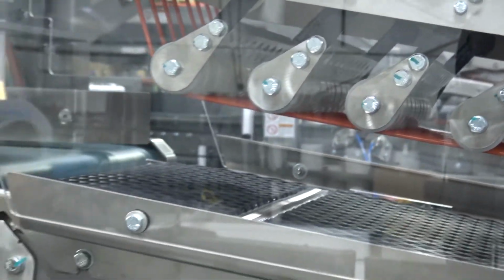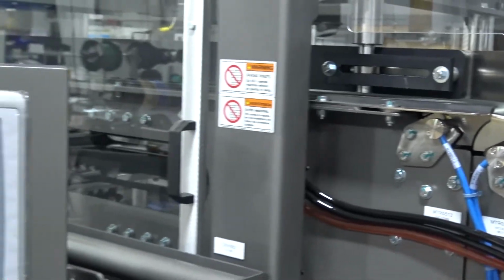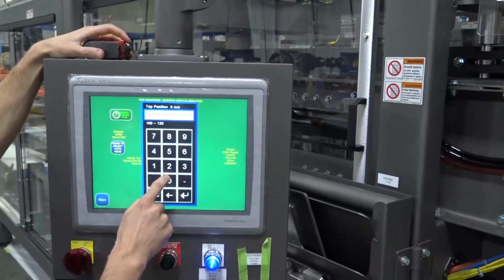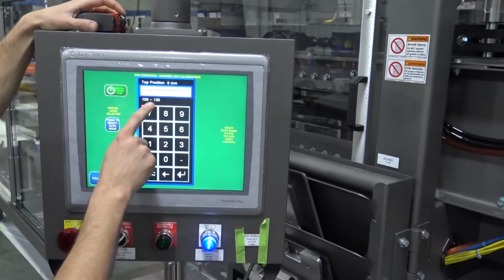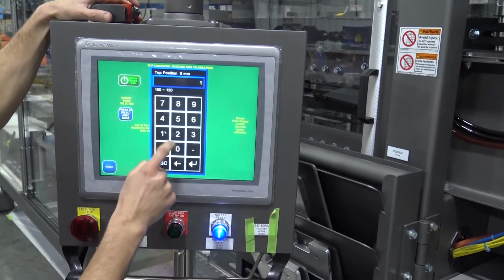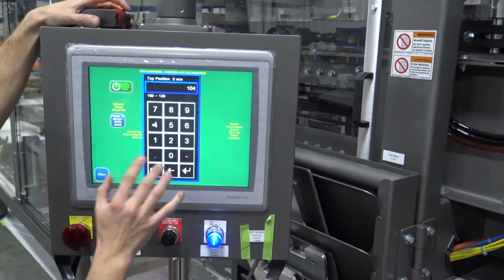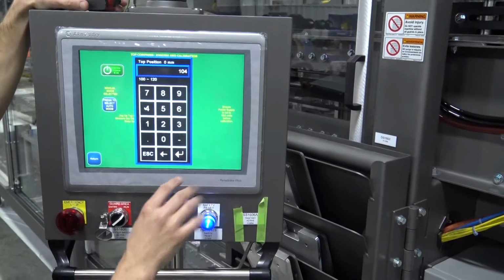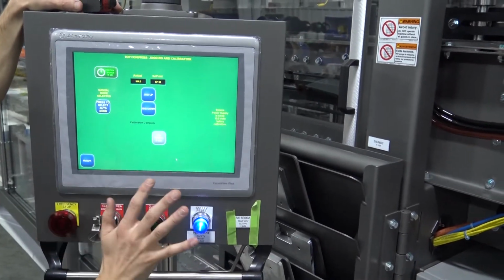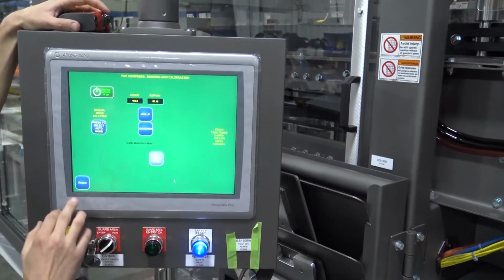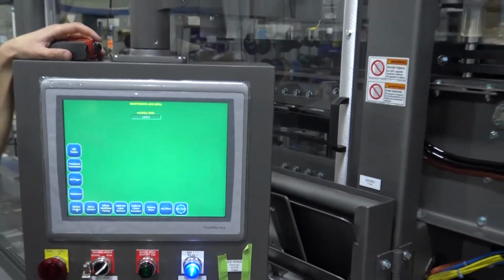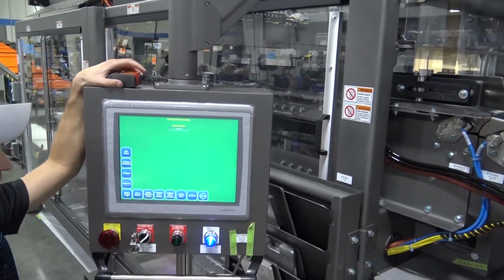I'm going to go back to the HMI, and I'm going to input that into the top position. So it's at about 104. There's your range, 100 to 120. That's what we measured, 104, and that's at the position it's actively in. And that's all you need to do. Calibration's complete, and you've calibrated the linear actuator for the bag stop. Thank you for watching.